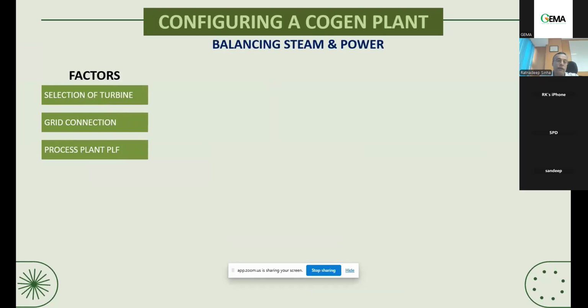So the factors while configuring a cogeneration plant are, first of all, the selection of the steam turbine, then whether you have a grid connection or whether you are going for a totally islanding mode of operation, cut off from the grid, and what the plant PLF is. Say you are sizing a 300 KLPD plant: what is your expectation, in the next 5 or 7 years after commissioning, will it run at 100% load, 80% load on average, or 75% of the load? You guys are in a much better position to judge that, but it also has to be taken into consideration. And based on your feed available and the amount of offtake you can deliver to the buyer, you also need to understand the fluctuation that is going to happen in your ethanol plant, because all of these affect the cogeneration plant sizing.